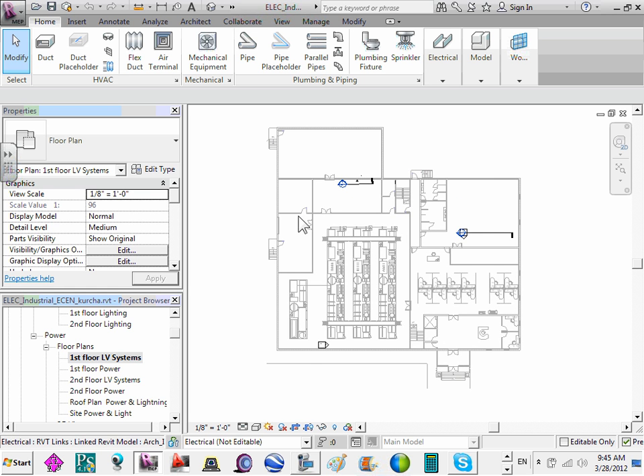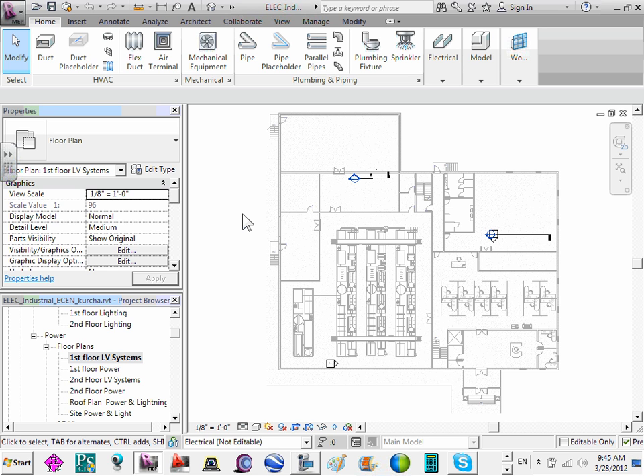In a building like this, a B occupancy, fully sprinkled, really no fire alarm system is required, except you're going to have smoke detectors for elevator recall, duct detectors for any air handling units over 2,000 CFM, and monitoring of the flow and tamper. Now that's not saying that's all you're going to put in here, but that's the minimum code requirement. Their insurance company may require them to have a full-blown fire alarm system. They may want one so they can get a reduced insurance rate, or just for notification of their faculty or whoever's working. So it all depends on what the owner wants. You're going to be talking a lot with the owner and dealing a lot with them.